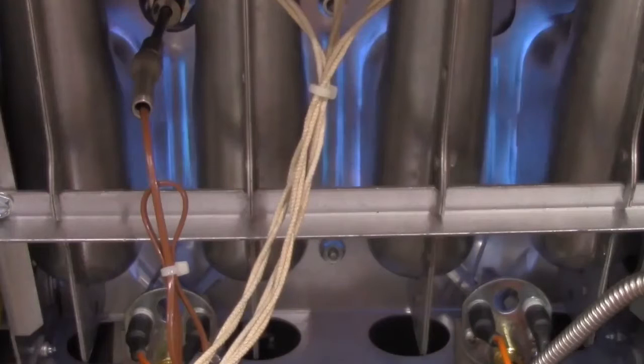So what did we say? Check our oil levels first, right? And then number 2, we could have them check to make sure that there's not anything going on with their atmospheric equalization hole, so make sure that's clean. As soon as they take that cap out and all of a sudden you get the main burn coming on and things are working good, it's a good chance that it's dirty and needs to be cleaned. If you have repeat issues with the oil, then we have that field fix that some technicians have informed us about that they've been doing, and it seems to be helpful. So there are 2 things that we can go through with it.